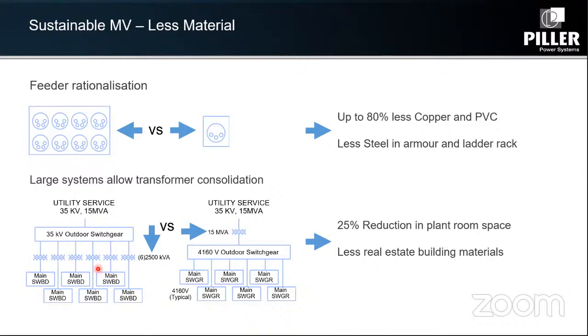This can all be consolidated if you use, I have a further breakdown, but in this presentation we are limiting to the concept. If you move it on a medium voltage, you have possibilities of transformer consolidation and reducing your overall losses. This comparison is for a 35 kV and a 4.1 from a customer in the US, but we have done this analysis for customers in India too.